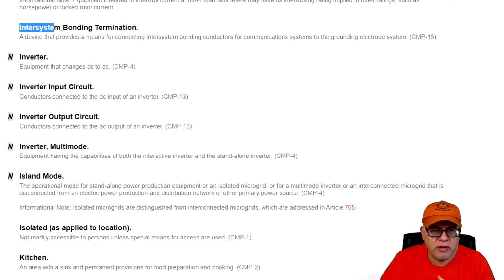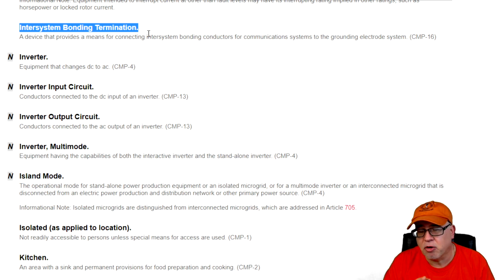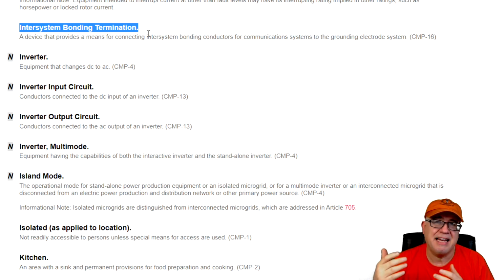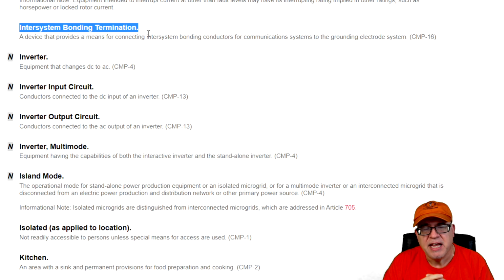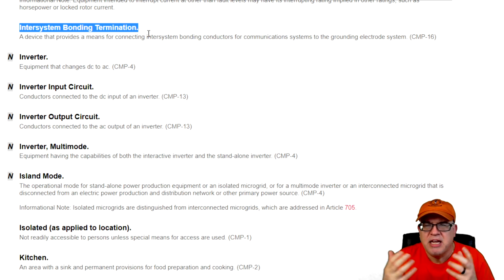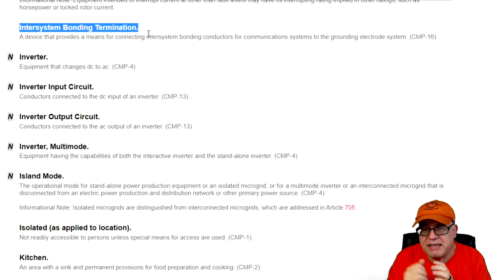Intersystem bonding termination. So this is that little connection that is made at your meter or service equipment and at detached structures that have communication systems and things like that, Dish Network, DirecTV, all those type of cable lines that come in. So we have what's called intersystem bonding, and that's connecting all of the connections for communication systems together and then connecting them to the grounding electrode system, generally for lightning dissipation and things like that. So that's called an intersystem bonding termination, that point on the system where you take all of those bonding conductors for all of these communication systems and you bring them together and then you connect them directly to the grounding electrode system. Okay, that's what an intersystem bonding termination is.